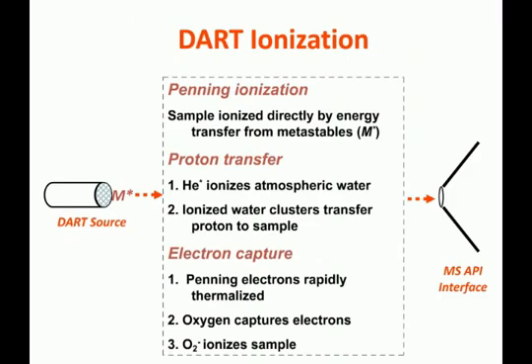To a first approximation, the first step is that electronically excited helium ionizes atmospheric moisture, and the ionized water clusters then can transfer a proton to a sample — that's the primary mechanism for ionization in positive ion mode. But in negative ion mode, the electron produced in the first Penning ionization step interacts with atmospheric oxygen, and the ionized oxygen then produces ions from the sample.